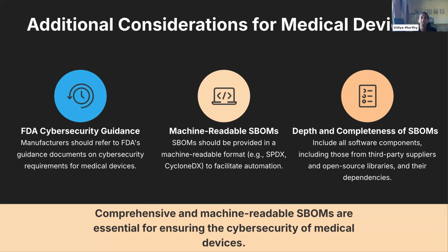There are additional things that have to be considered when we think about devices. The FDA wants it to be a machine-readable SBOM, so when you submit it to them, they expect it to be consumable in either SPDX or CycloneDX. Those are the two that we most frequently see. They don't explicitly say which format they want, but they say it has to be machine-readable, and you have to consider that in what you're providing.